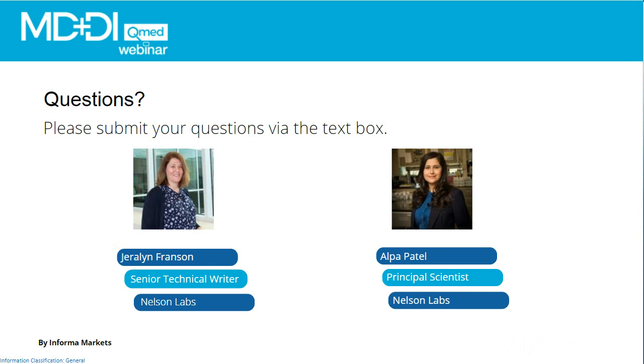How does life cycle testing play a role in reprocessing, and is this test required? With life cycle testing, like I said at the end of my presentation, in ISO 10993 the language used shows it's required. However, there are other documents that specify that as long as you inform the user in your IFU how to identify that the device is no longer usable, then you are fine and you don't have to perform the cycles.